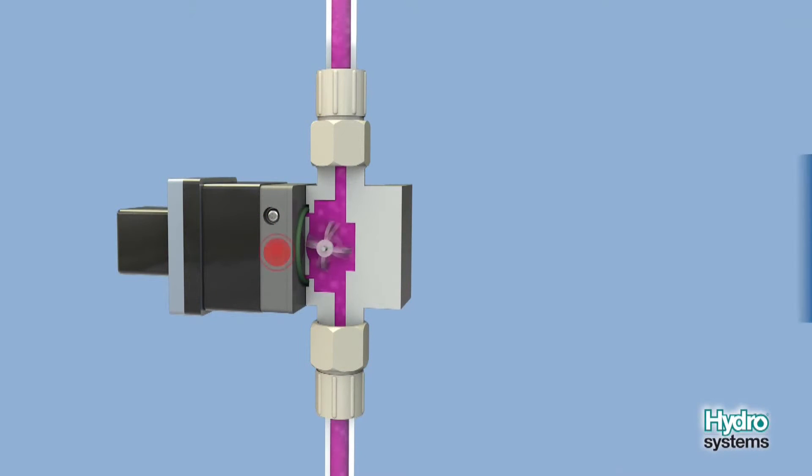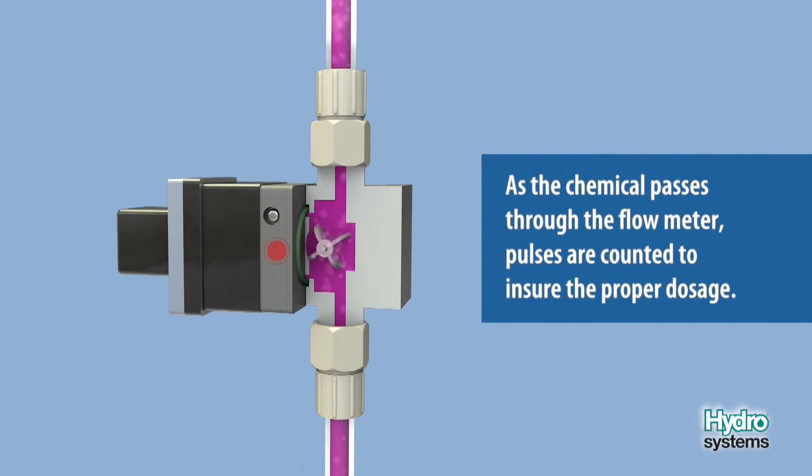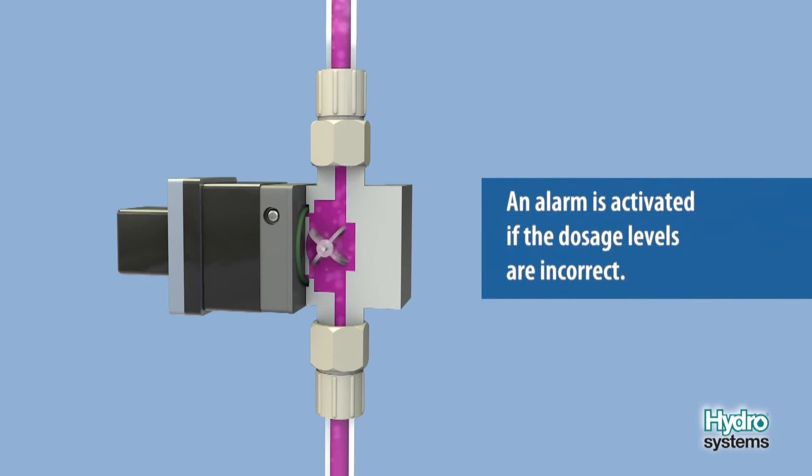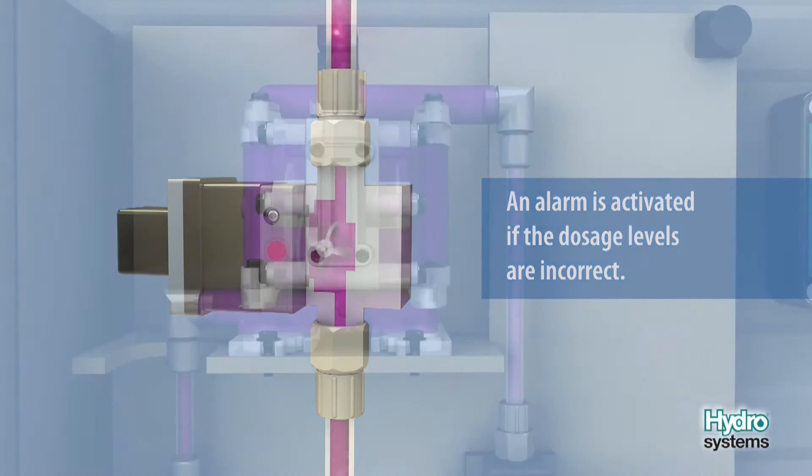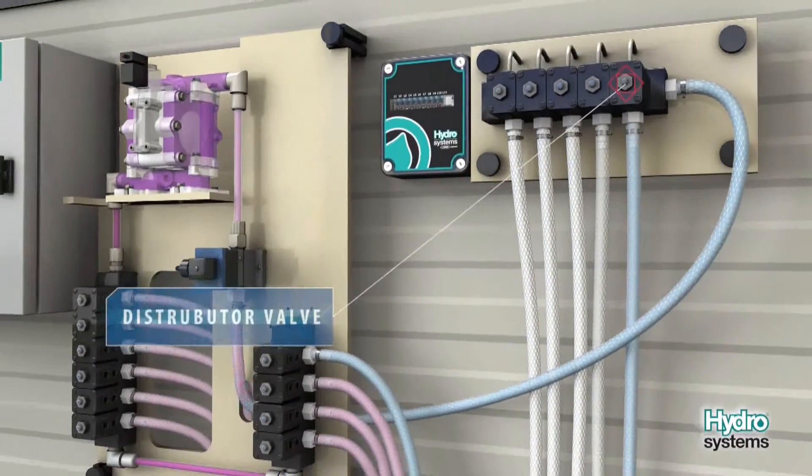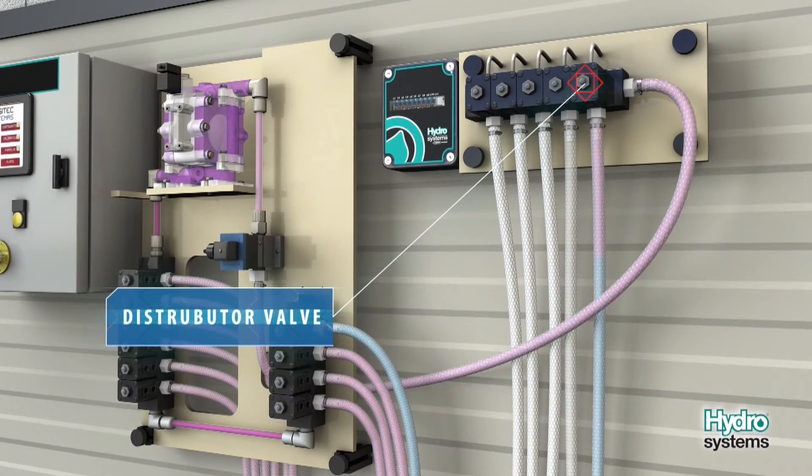As the chemical passes through the flow meter, pulses are counted to ensure the proper amount of chemical is dosed. If the desired number of pulses are not received in an appropriate time period, an alarm is activated. As the product reaches the distributor valve, it is dispensed to the machine.